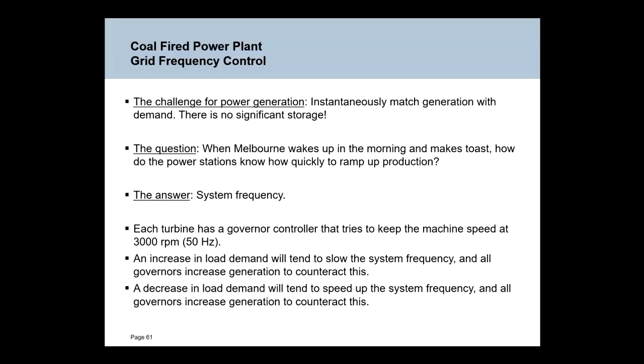Conversely, when we turn lights and toasters off, the system frequency starts to increase because we've reduced the braking force on the system, and they all back off the coal and the gas firing in order to bring the megawatts back to where they need to be. Does that make sense? That's a very important basic concept in power generation that people don't understand. I think it's quite simple to understand when someone explains it to you. Okay.